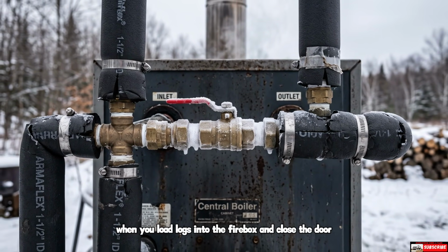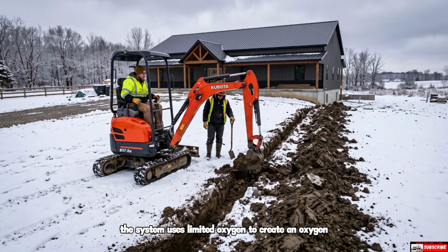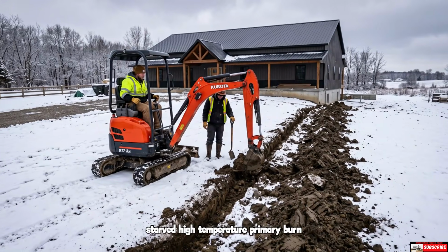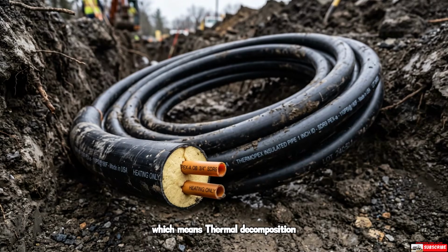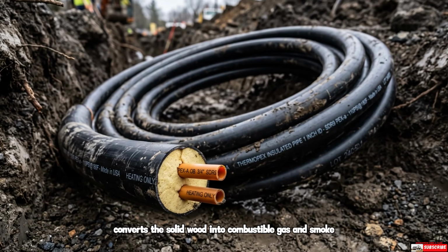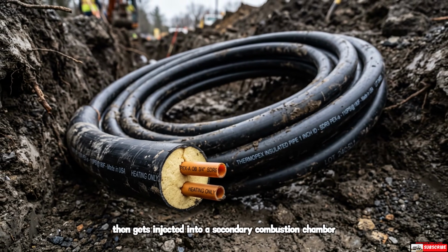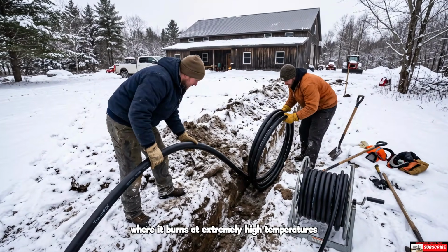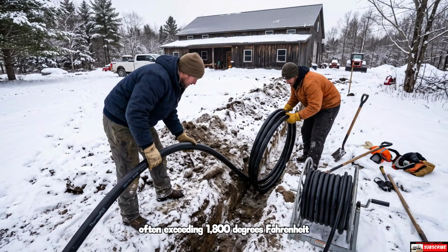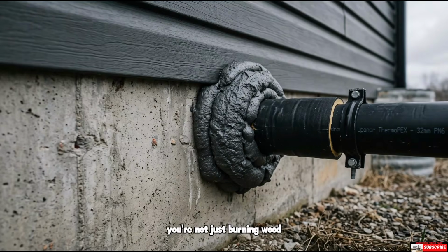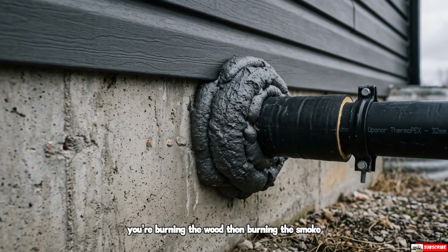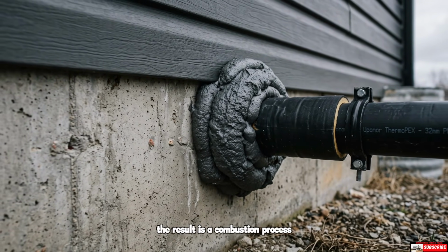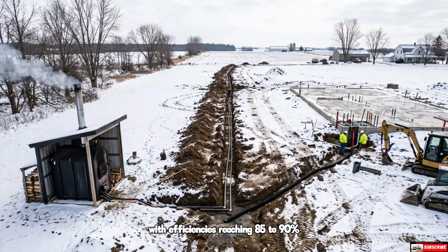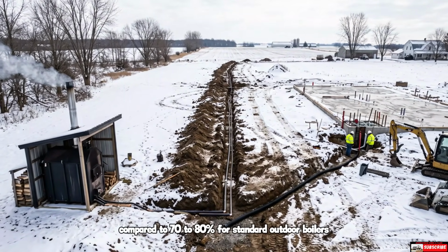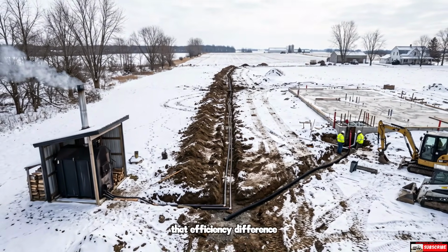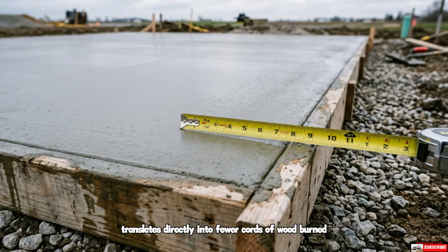When you load logs into the firebox and close the door, the system uses limited oxygen to create an oxygen-starved, high-temperature primary burn. This pyrolysis process, which means thermal decomposition, converts the solid wood into combustible gas and smoke. That gas then gets injected into a secondary combustion chamber, where it burns at extremely high temperatures, often exceeding 1,800 degrees Fahrenheit. You're not just burning wood, you're burning the wood, then burning the smoke, then burning the gas produced from that smoke. The result is a combustion process with efficiencies reaching 85 to 90%, compared to 70 to 80% for standard outdoor boilers. That efficiency difference translates directly into fewer cords of wood burned per season.